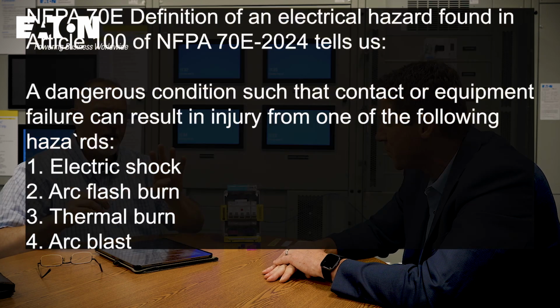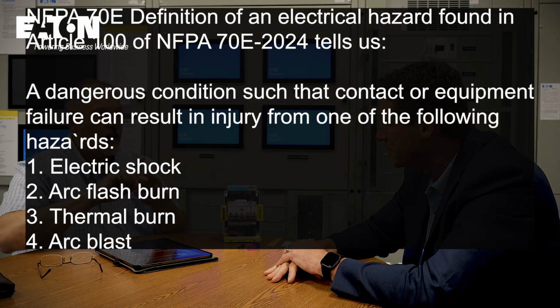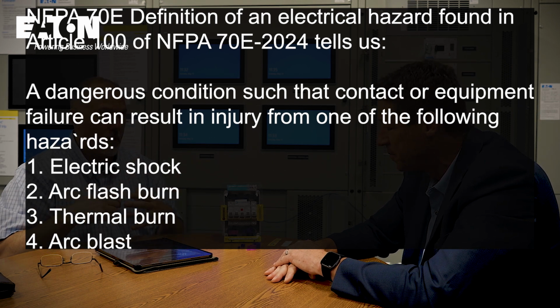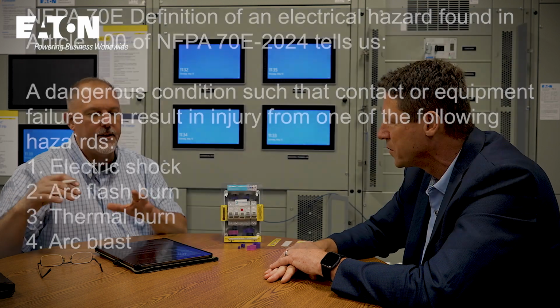Personal protective equipment is there to protect you from a thermal injury, not from the blast. If you think about it, there are four hazards in 70E: arc flash, arc blast, shock, and thermal burns. They keep those separate. The thermal burns are like low voltage DC applications that won't cause an arc flash or kill you from a shock perspective, but current through something metal can make it pretty hot.